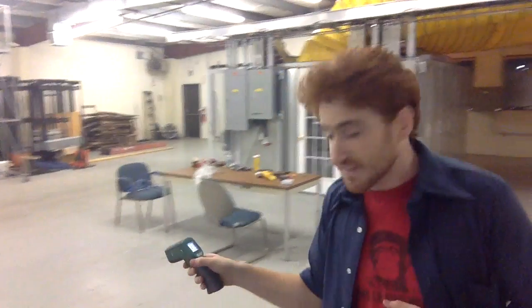And in here we have our data center. We have temperatures of about 21 degrees, 21.5, 21.7, something like that on our floor. And this is without any air conditioning whatsoever. There's probably wind noise here. Move back a little bit. So we have no air conditioning in this entire building, or in this entire warehouse room. Everything is done using evaporative coolers, which use only water and a little bit of electricity to run a fan. This is much more efficient than air conditioning can be and allows us to keep our costs low. And frankly, the performance is quite good.